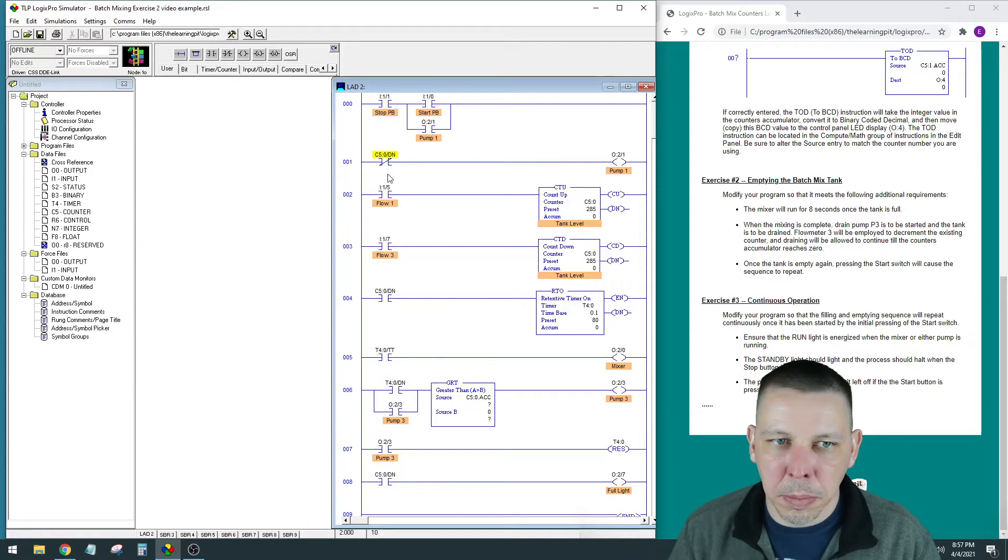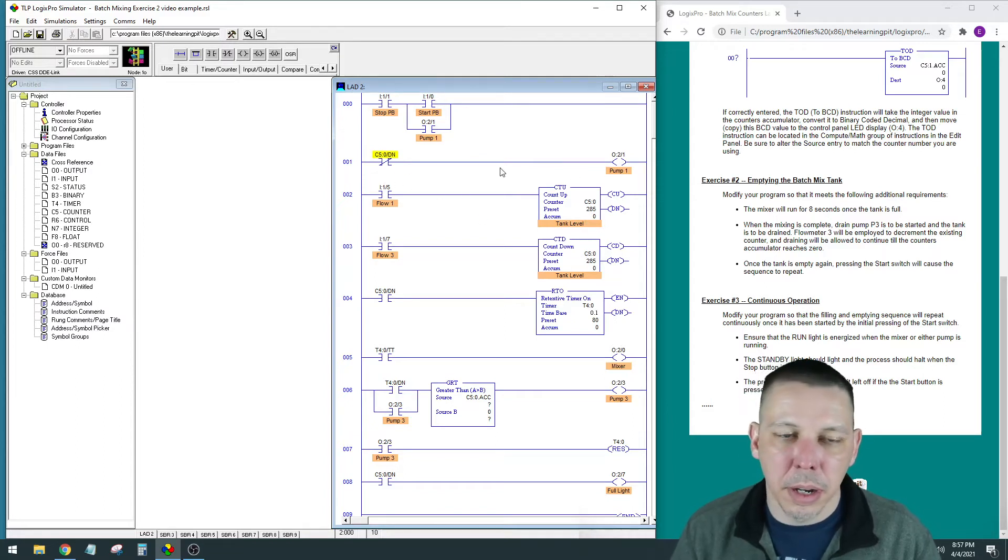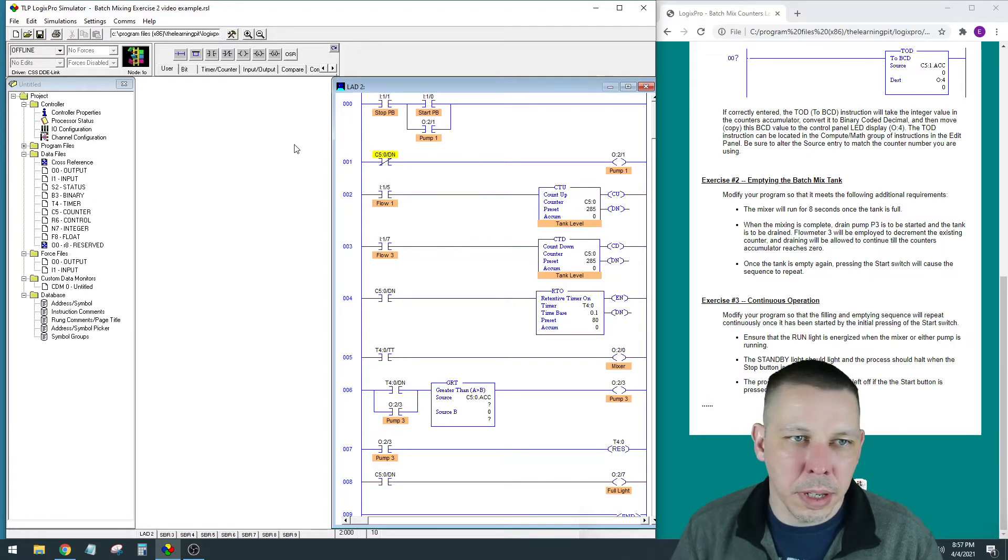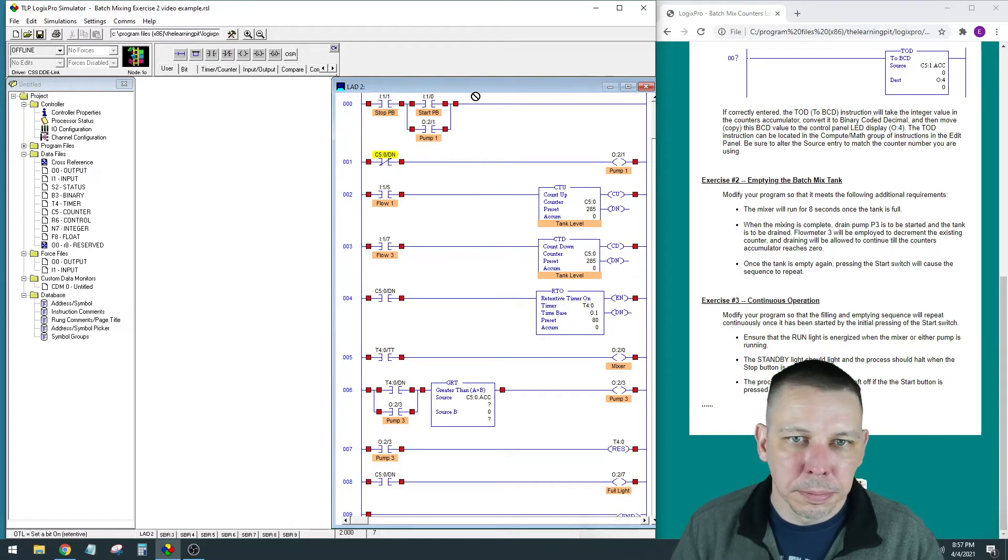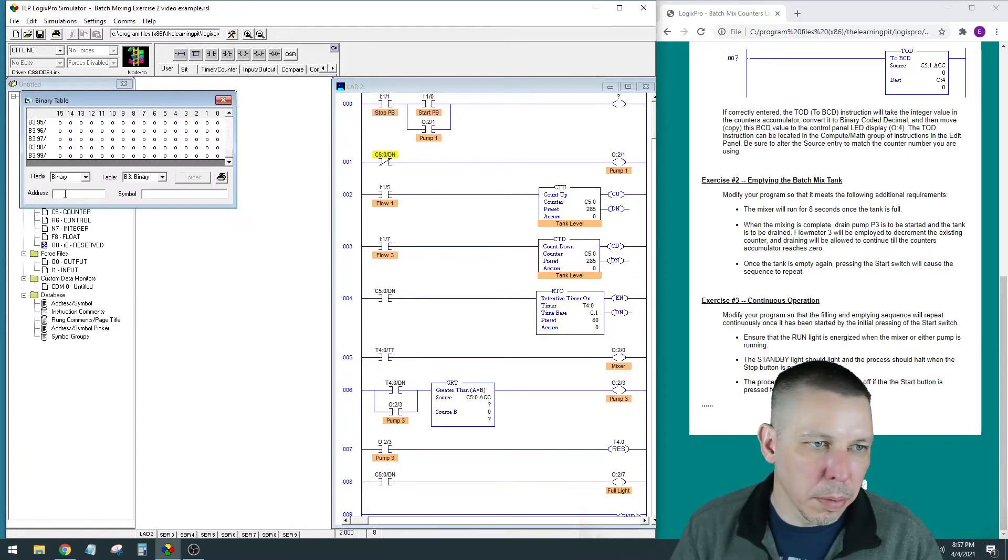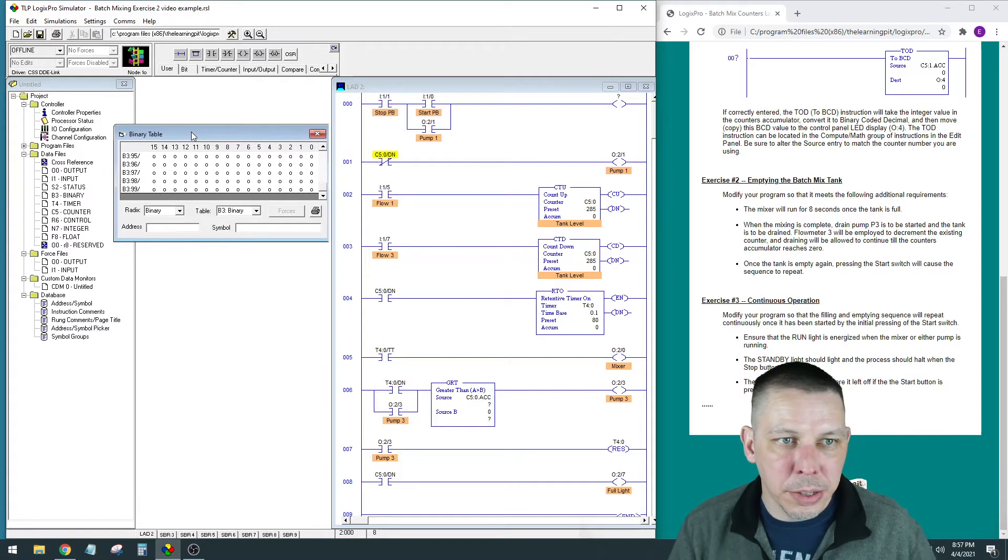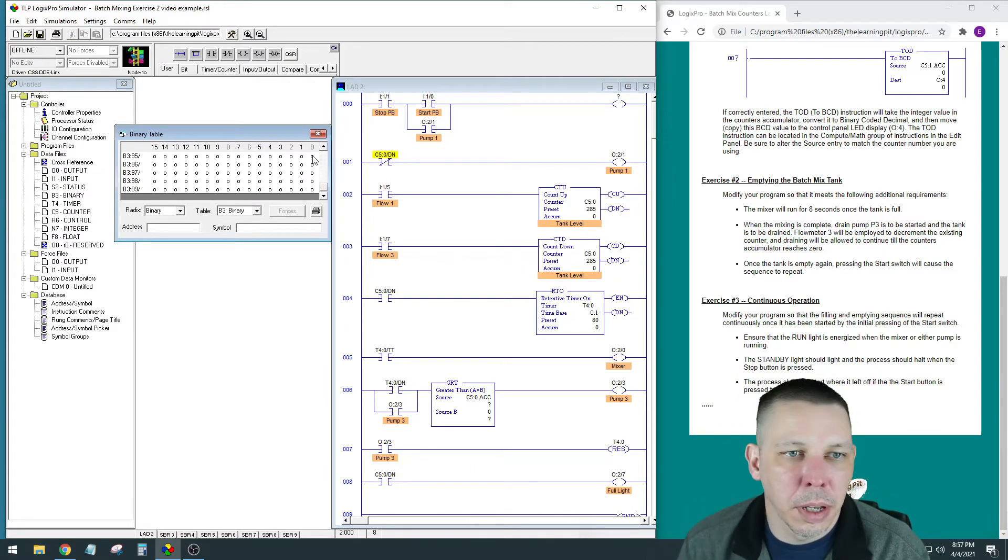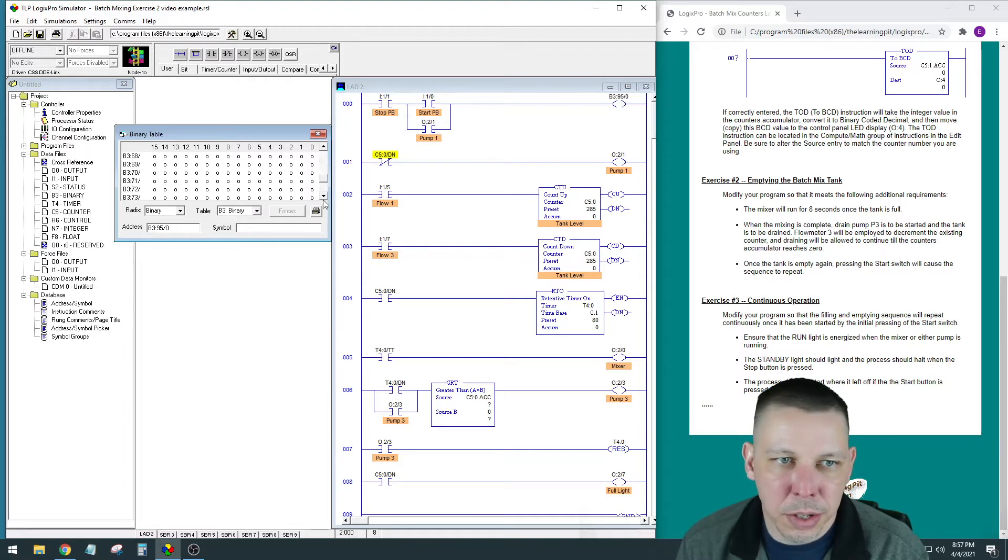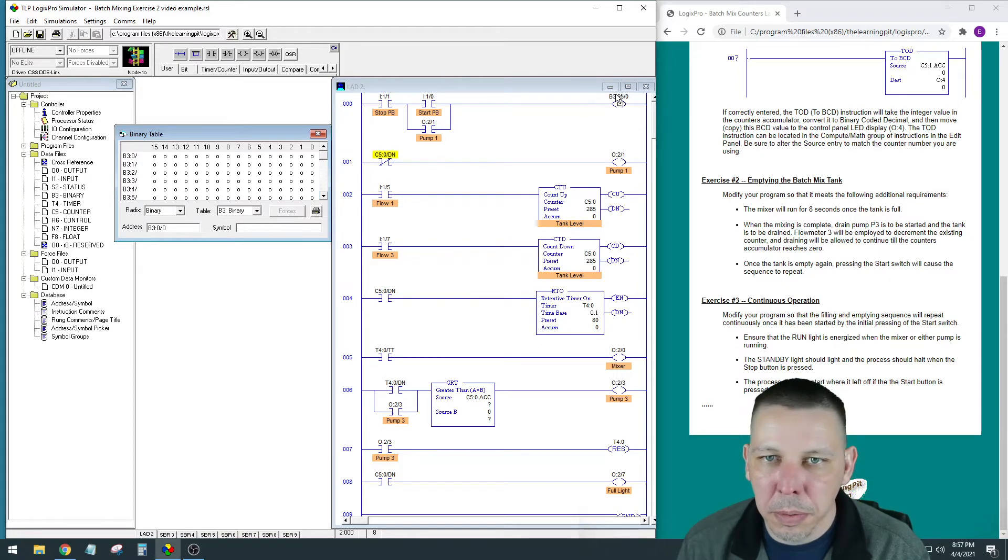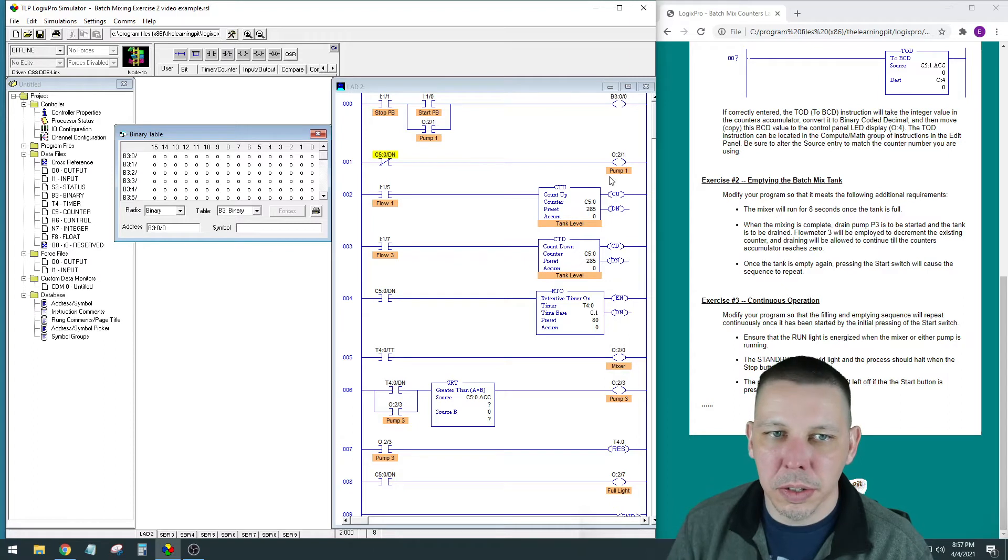I'm going to move this guy down here for now, and I am going to move this guy down here too, because we only want the pump to run until this count up gets to 285, till it fills up to 90%, right? And then this stop/start is going to stay the same, and I'm going to put a B3 bit here. These are memory locations that you can use—this is a binary table, so these are bits.